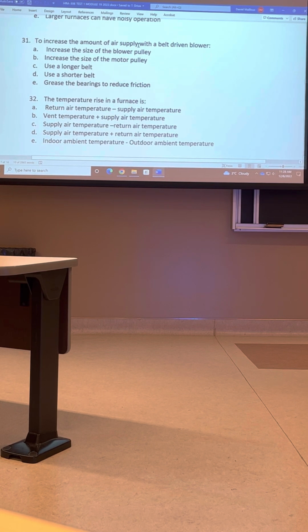To increase the amount of air supply with a belt-driven blower, so you've got a belt-driven blower and you need more air, we increase the size of the motor pulley. If the pulley on the motor is a 3 1/4, typically on most you get around 800 CFM. If you need like 1200, you can take that 3 1/4 off, put a 4 1/4 on, and you'll get more air.